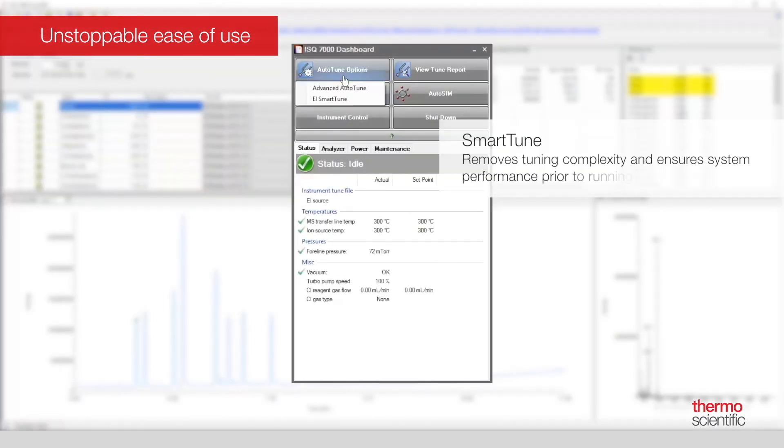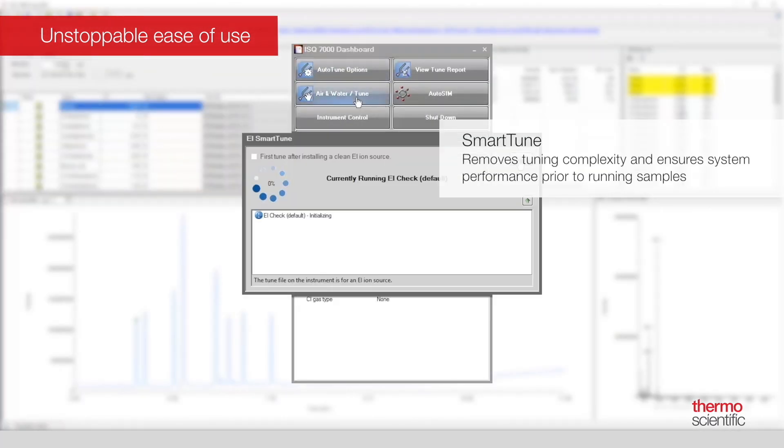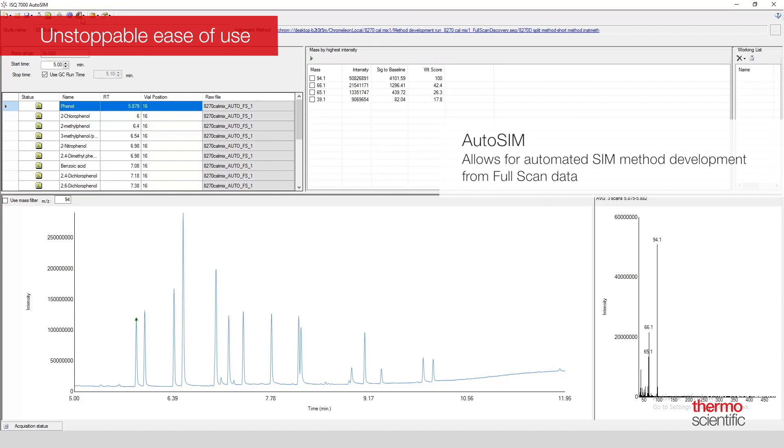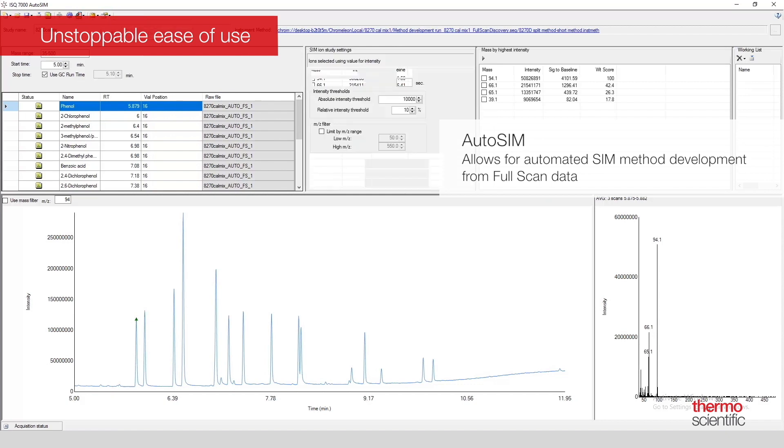SmartTune, our new simplified tuning tool, intuitively removes tuning complexity and ensures your system is performing at the level you require ahead of running your samples. If a problem is detected, SmartTune advises you on recommended corrective action. AutoSIM allows you to acquire full scan data, enter or import from an external file your list of target analytes, and perform selection of the SIM ions from the full scan data in a guided, automated fashion.